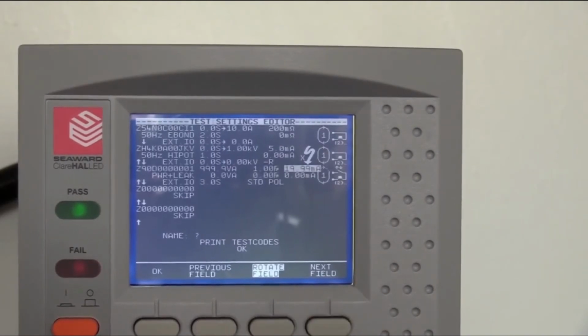We can also set our leakage value. Again, dependent on the test you want to perform, you can set a lower leakage in accordance with the standard and an upper leakage if prescribed. These aren't always necessarily set for routine tests, but there are some values for 60335 we could set in accordance with the standard. In this case, we'll assume we're testing something that is portable. So we'll set the limit to 3.5 milliamps.